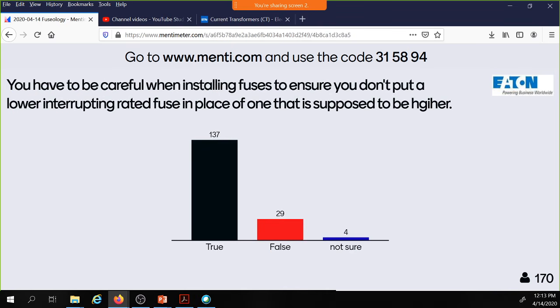So you have to be careful when installing fuses to ensure you don't put a lower interrupting rating fuse in place of one that is supposed to be higher, or higher. That's a new word. I got to put that in my dictionary. Hgiher. Was supposed to be higher.